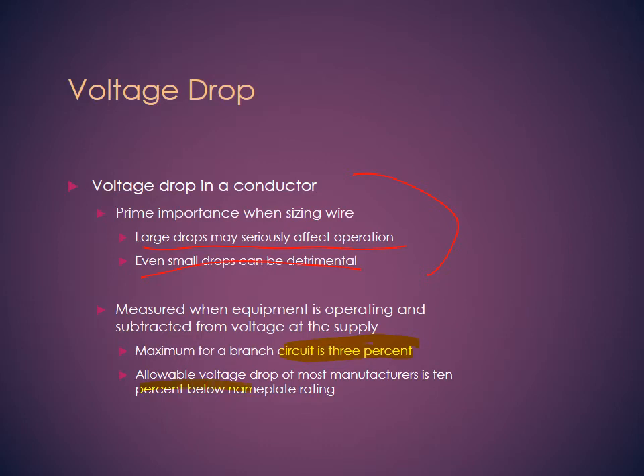For 10% is coming to the equipment. If I want to talk about the branch, let's say this is my control panel. I have a wire coming all the way to the burner here, and this is a branch that's operating, let's say, an inducer fan motor. The drop from here to here should not be more than 3%, and the drop on a main line, from here to here, should not be more than 10%. And again, inferior cables, inferior wires, have a lot of resistance, so you should pay attention to that. Also look at the resistance and the voltage drop per foot.